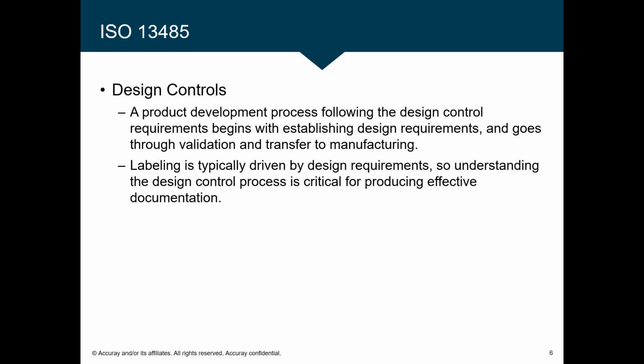The other component of 13485 that impacts labeling is design control. When you have a product development process, you need to follow the design control requirements, which start with establishing what the design is going to be, the requirements and specifications for developing that product, then validating the design, and then transferring that to manufacturing.